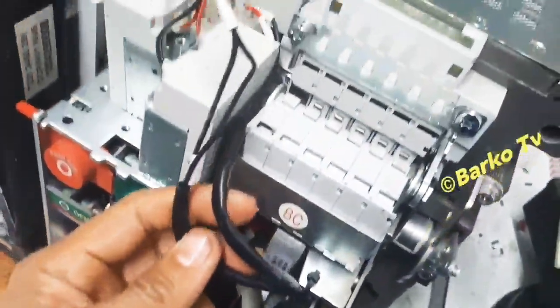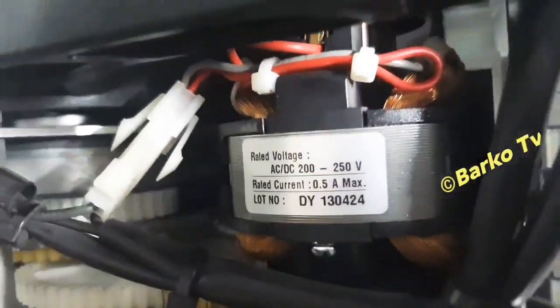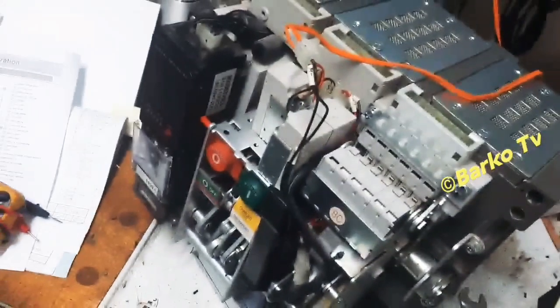For the motor, M-plus and M-minus are only indicators — there is no polarity because the motor is AC. Previously we used the lever for manual charging; right now we simulate the actual motor charging.